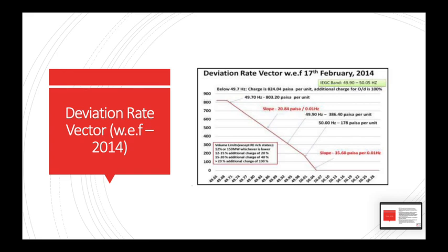Now this 15 megawatt which I have delivered less, if I compute in terms of units, would come to approximately 15 into 1000 divided by 4, since I have to convert into hours, so it comes to approximately 3750. So these 3750 units which I have dispatched less, though the state will pay me the money for the fuel for the schedule which the beneficiaries told me to dispatch, since I am not able to dispatch, I have been given a penalty.